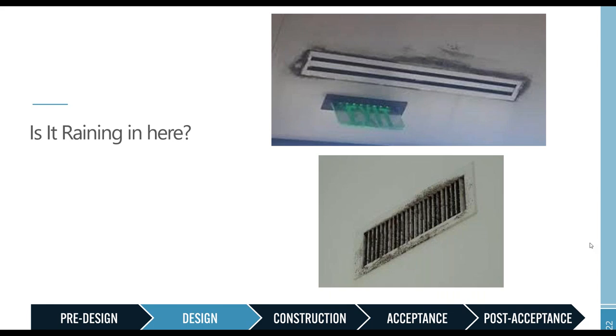So during design reviews, we call out diffusers in precarious locations where this may occur. In some cases, we recommend window or door switches to disable the AC units while the doors or windows are open. In more extreme cases, modifications to the control sequence or mechanical equipment selection is recommended. These precautions typically protect us from this messy situation during startup and operation.